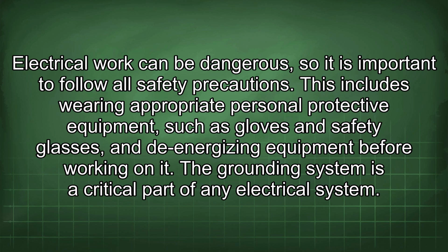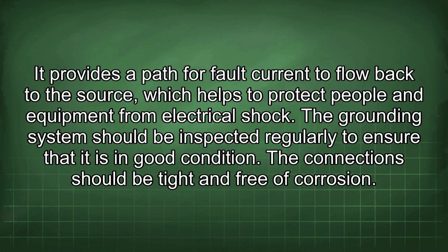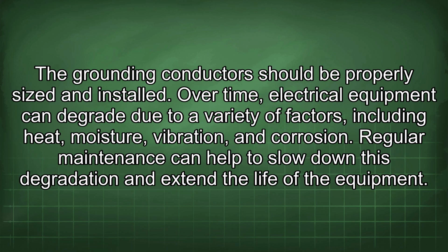The grounding system is a critical part of any electrical system. It provides a path for fault current to flow back to the source, which helps to protect people and equipment from electrical shock. The grounding system should be inspected regularly to ensure that it is in good condition. The connection should be tight and free of corrosion. The grounding conductors should be properly sized and installed.